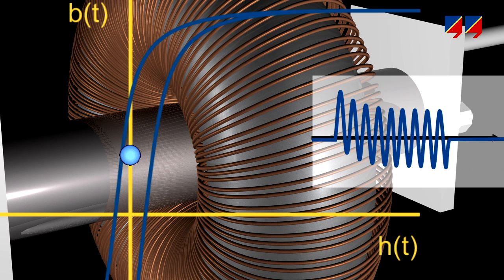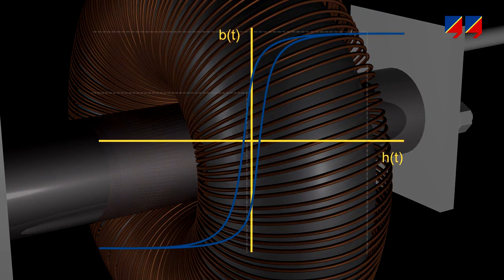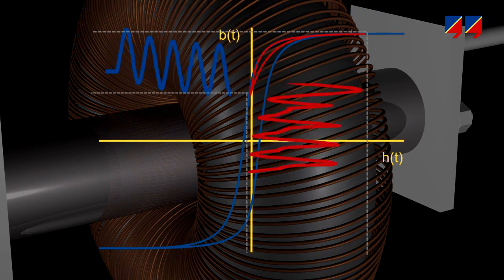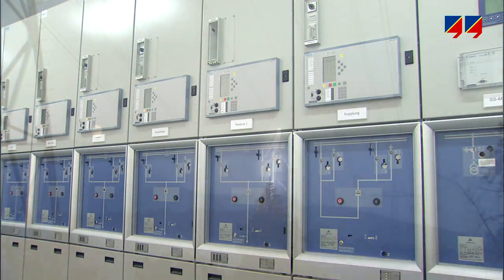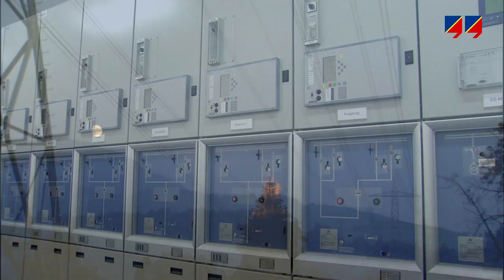With each cycle, magnetic flux from the fault condition is added to a growing remanent flux from previous cycles. At some stage, the CT will not transform the fault current correctly, preventing the protection system from clearing the fault quickly, or in the worst case, not at all.